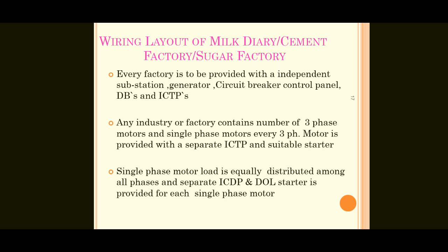Single-phase motor load is equally distributed among all phases, and a separate ICDP and DOL starter is provided for each single-phase motor.